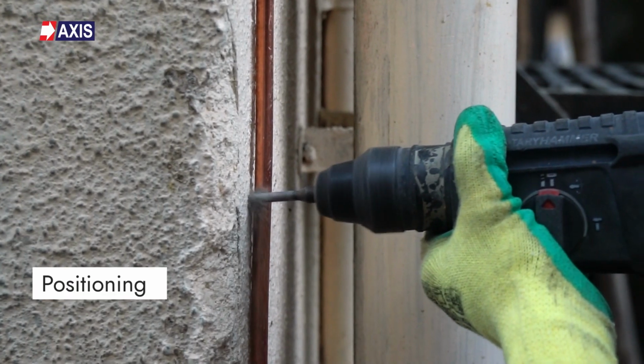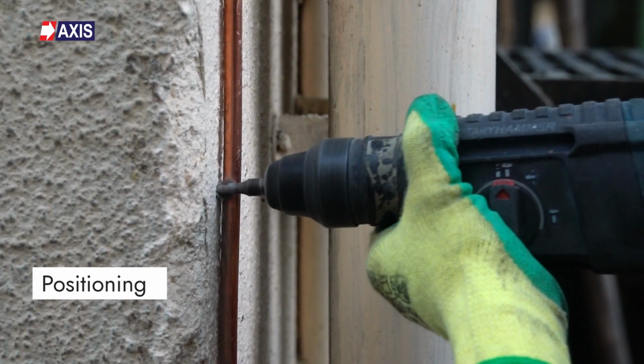Number 3, positioning. The distribution of down conductors around the perimeter of the structure, starting at the corners, ensures an efficient pathway for the lightning current to the ground. Poor positioning could lead to inefficient current discharge, possibly causing overheating and damage to the structure or even a fire.